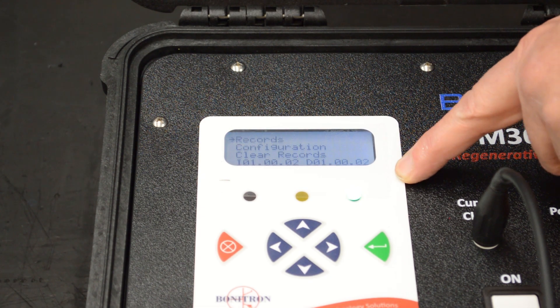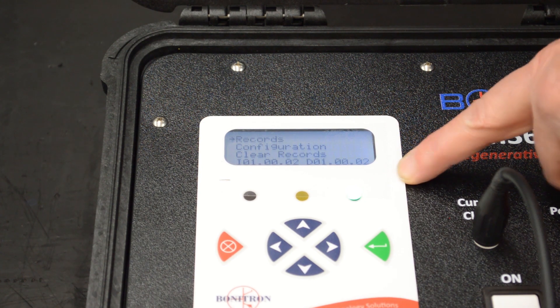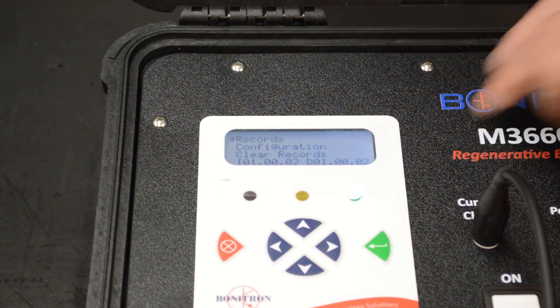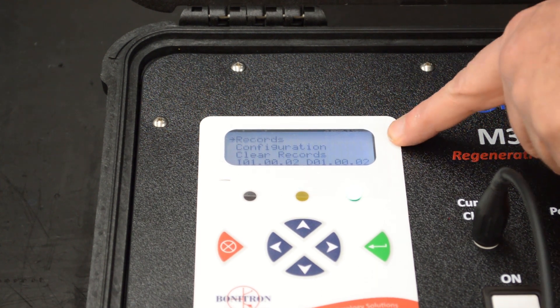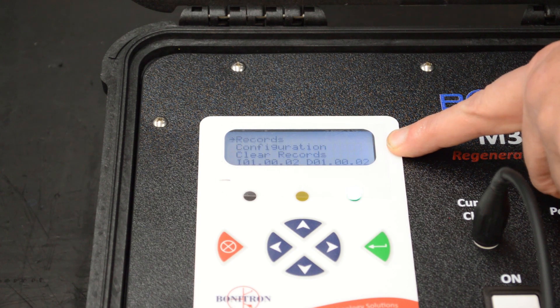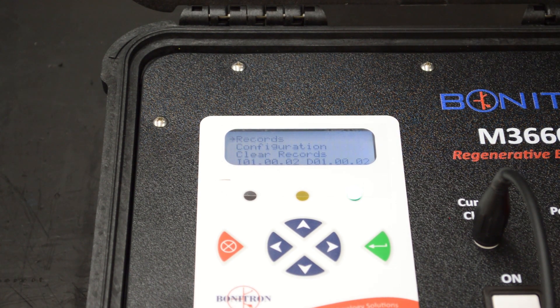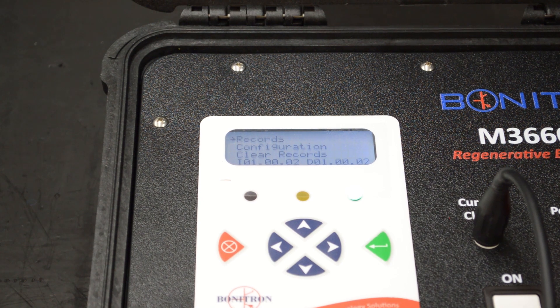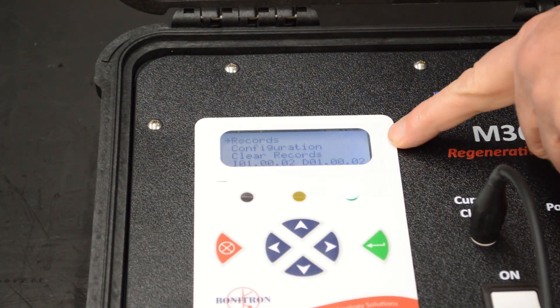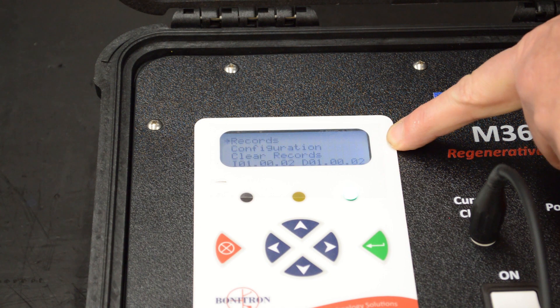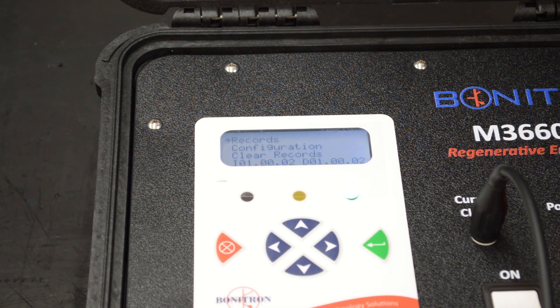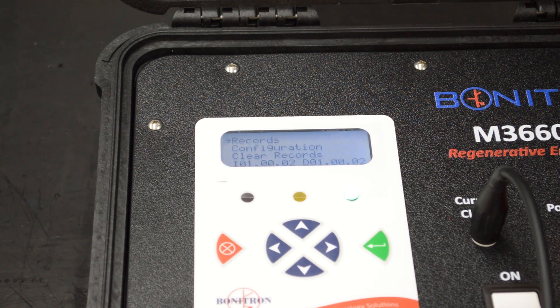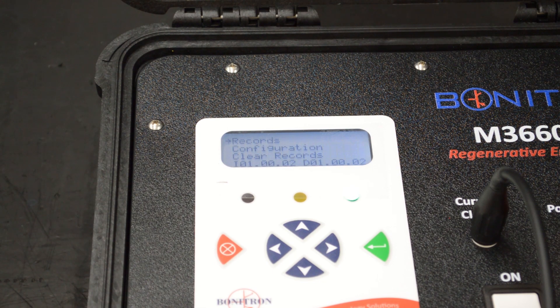Now we're going to talk about the menu and the display and the different menus you have. When you first power up, hit the on button and you're going to have three menus. One that shows you records, and this is a record of the regenerative energy and the events that you do when you're monitoring the DC bus for regen. And then you have a configuration which sets this up and configures it. And then you also have to where you can clear records and start all over again. This will monitor one event and tell you what the one event regen energy was, and it will also monitor over a period of time cumulative regen energy from the total events.